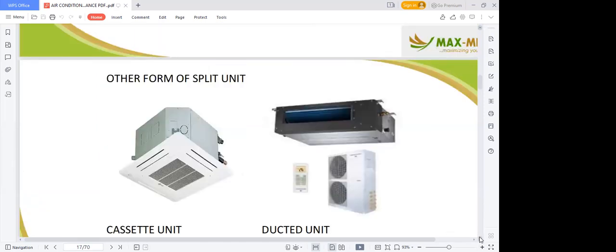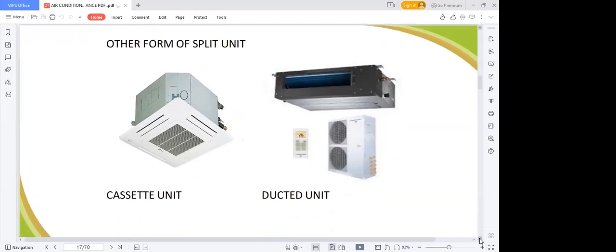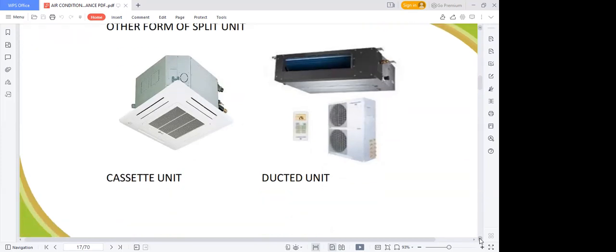Then the fancy type. You might have a client that will tell you, I don't need split, I don't need window, I need something off my ceiling. Then you can give them something similar to this, if they have enough headroom. The problem with this is the drain. Every such unit has a pump that pumps water from a lower area to a higher area. This back is the return and supply refrigerant line that is bringing the cool and taking the hot refrigerant gas out.